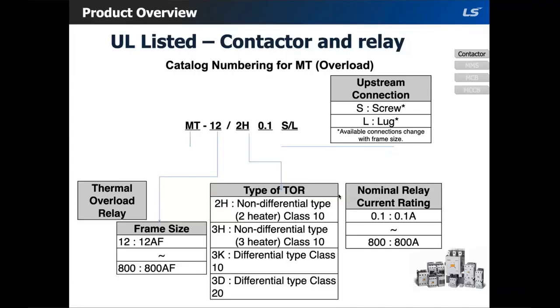So for example, if you're using a non-differential overload, it could allow a motor to be single-phased. If one of the phases drop and the current remains below the threshold for tripping, this will cause premature failure of the motor. So to be safe, I would recommend using differential because it has a phase failure detection.